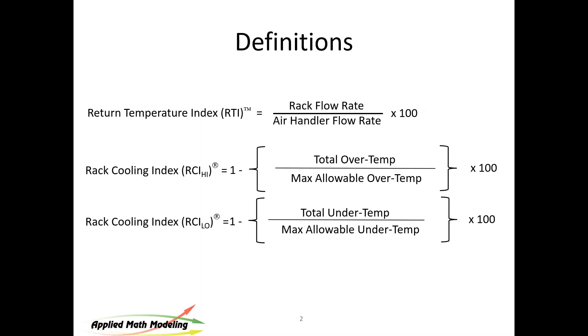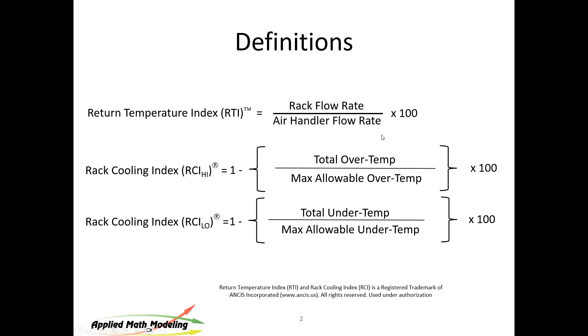The other metric is Rack Cooling Index — RCI. There are two: RCI high and RCI low. RCI low is not really an issue, but RCI high tells you the number of hotspots and how far out of compliance you are with recommended rack inlet temperatures. We calculate these metrics in CoolSim's output report. A perfect design has all metrics at 100 — no hotspots, no excess air, and inlet temperatures within ASHRAE recommended range.